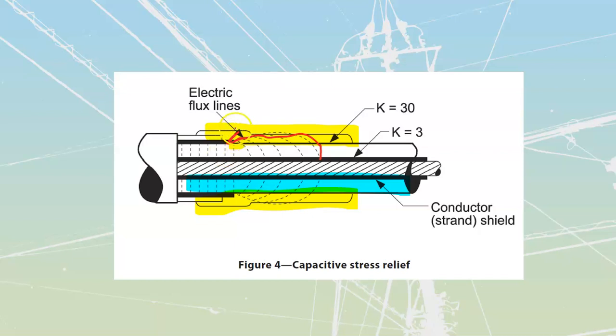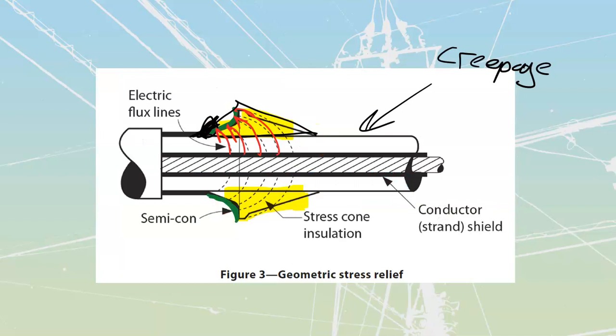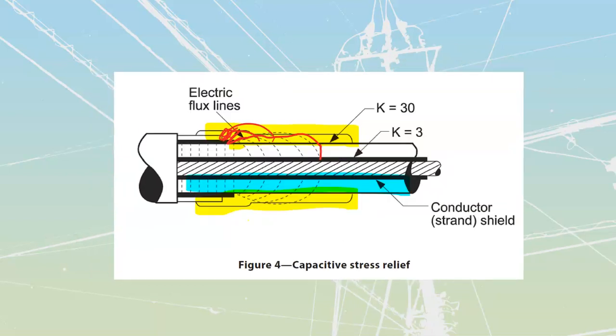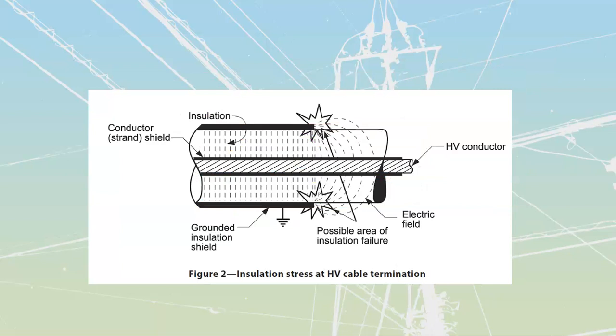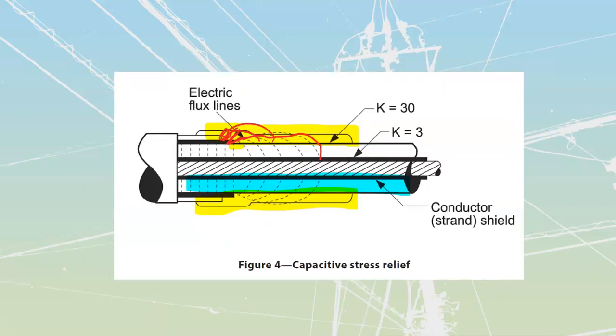At that point, all of my flux lines would be combined inside of this tube, but this tube is able to withstand it. It's another way we can distribute our lines of electrical flux. It doesn't matter whether you're using geometric stress relief, high K stress relief, or wrapping that cone all the way around - all we're ever trying to do is distribute those lines of flux across there.